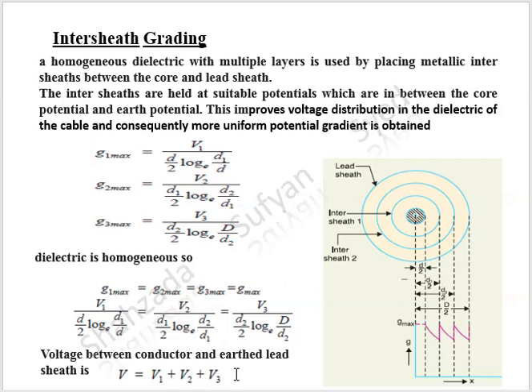The next method of grading is inter-sheath grading. In this method, a homogeneous dielectric with multiple layers is used by placing metallic inter-sheaths between the core and the lead sheath, held at suitable potentials between the core potential and earth potential. This improves voltage distribution in the dielectric and gives a more uniform potential gradient. Applying the G_max equation to each layer: G₁_max = V₁ / ((d/2) × log(d₁/d)), and similarly for G₂_max and G₃_max. Since the dielectric is homogeneous, all gradients are equal, and the total voltage between conductor and earth is V = V₁ + V₂ + V₃. Dear students, that was all on underground cables — hope you understood the topic, and if you have any questions, you can ask in the comments.